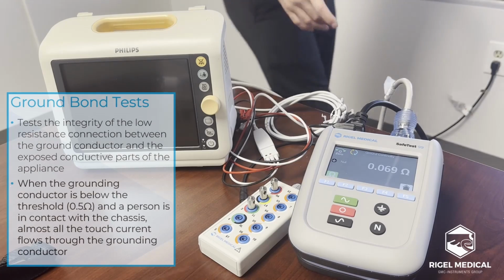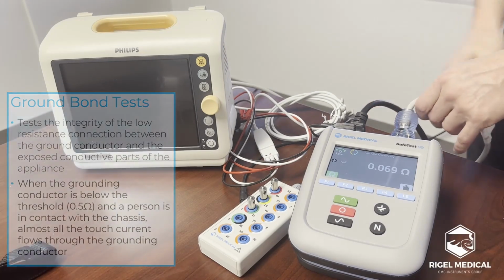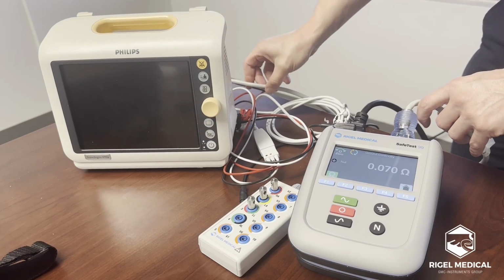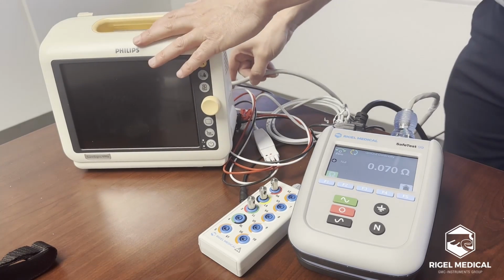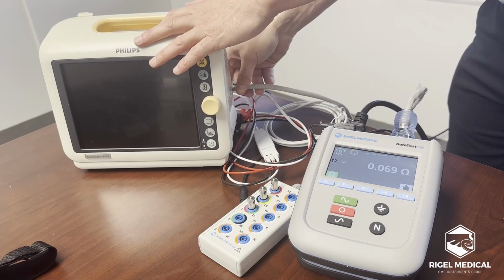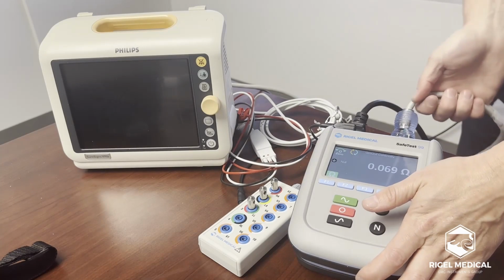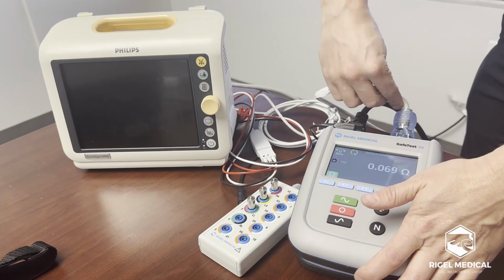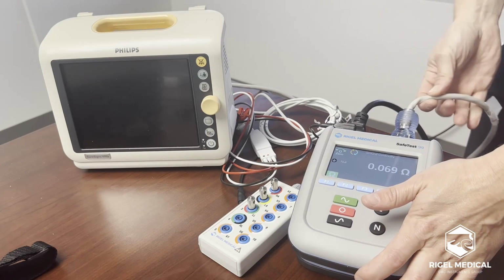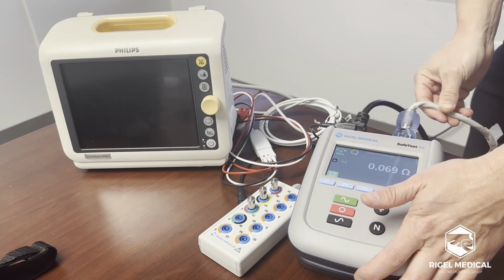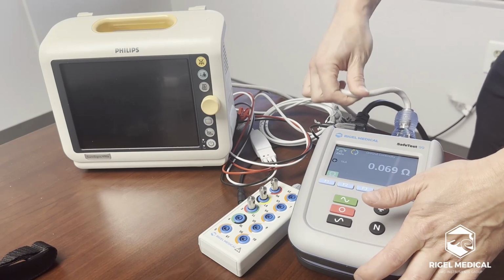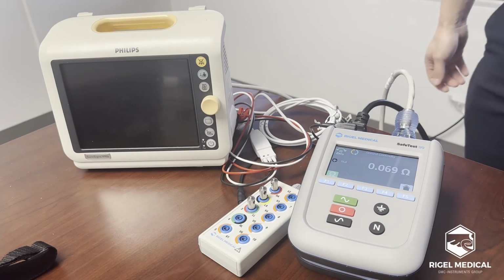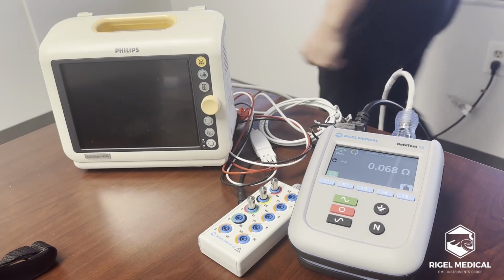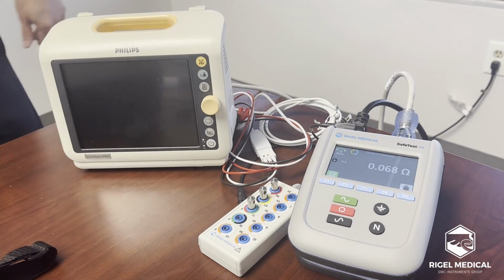Now I can check the lead for stress relief just by moving it around a bit to see if it's still within those limits. So I'm creating some stress on the leads, and it's still looking pretty good. So that's a good IEC lead there. We're not getting any issues. So okay, we're happy with that. Ground continuity test has passed. We can now move on to the next test.